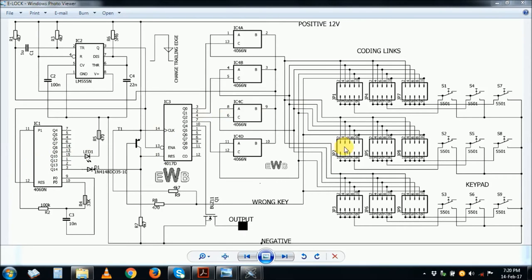Or right, if you press in a wrong key, which is a digit which is not within the code, you will notice that you have a reset condition also on the counter. This is how it is done. You program the wrong keys with shorting the position number 5. Position number 5 is only there to actually reset the counter when a wrong key is pressed. So position number 5 can only be the only one existing on each switch set or the cluster.